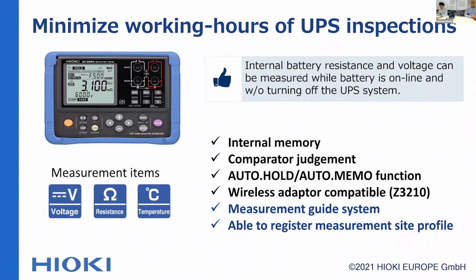This is the product overview. HIOKI believes minimizing working hours is an important benefit to battery maintenance customers. The basic test items for battery maintenance are battery voltage test, battery internal resistance measurement, and temperature measurement. These parameters can be measured while the UPS is online, and it can judge the battery conditions using the comparator function.